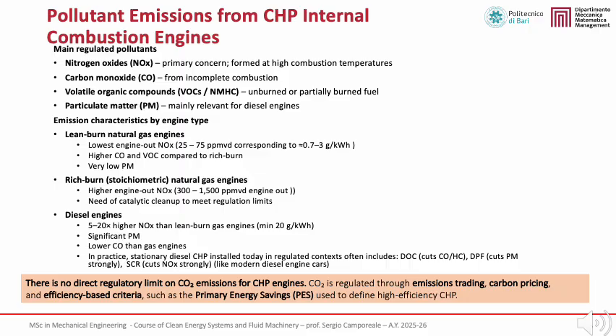Emission characteristics strongly depend on the engine type. Lean burn natural gas engines exhibit the lowest engine-out NOx emissions, typically between 25 and 75 parts per million, corresponding to approximately 0.7 to 3 grams per kilowatt hour. Compared to rich burn engines, they generally show higher carbon monoxide and VOC emissions, but very low particulate emissions. Rich burn, stoichiometric natural gas engines produce much higher engine-out NOx, often in the range of 300 to 1,500 parts per million. For this reason, they require catalytic aftertreatment, typically a three-way catalyst, in order to meet regulatory emission limits.